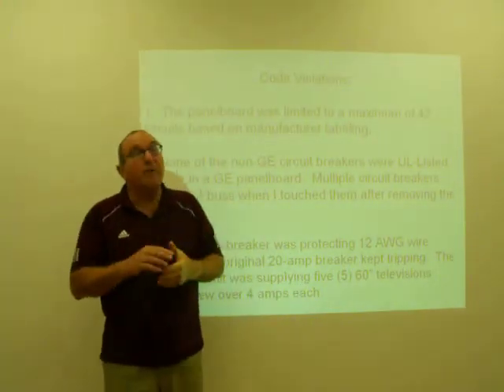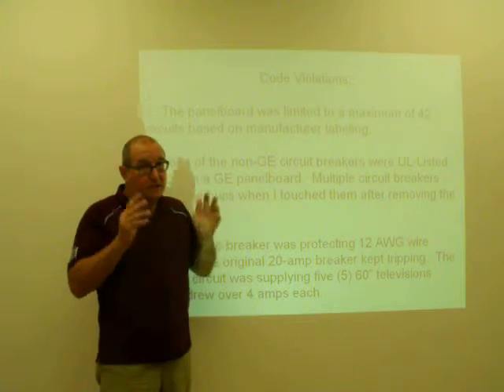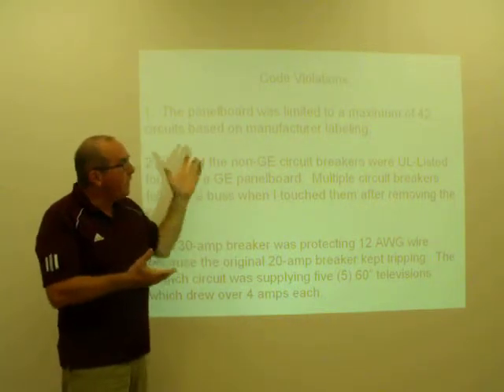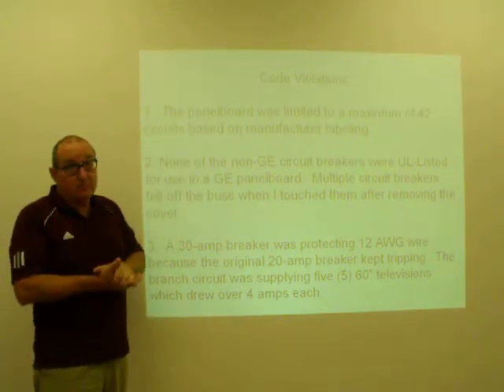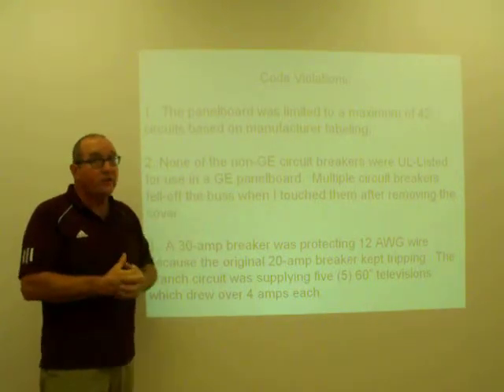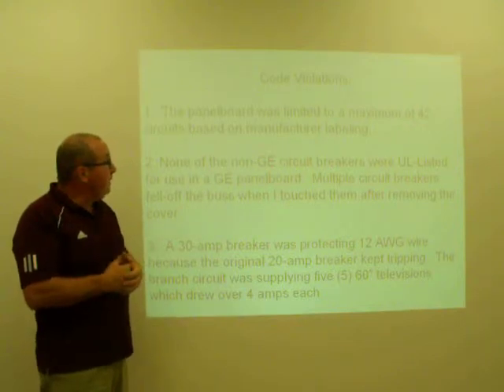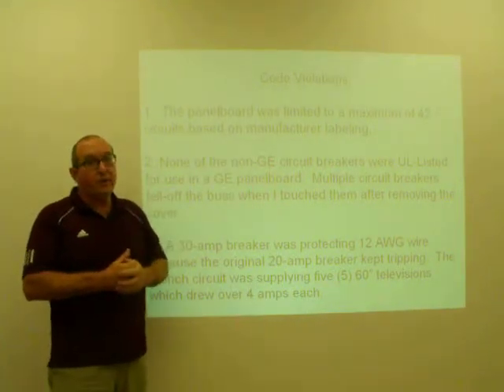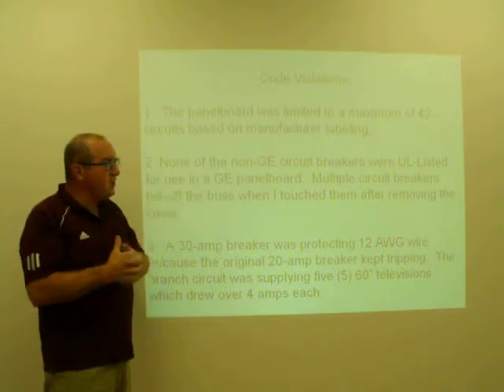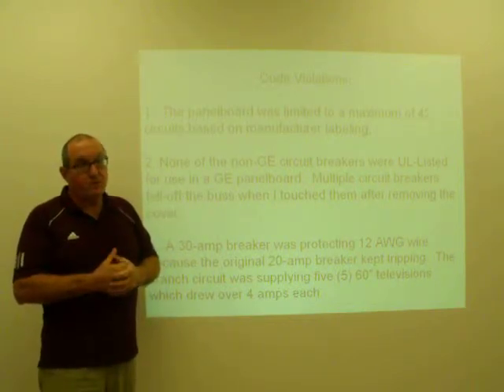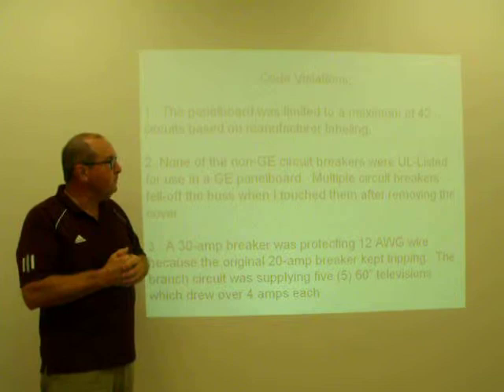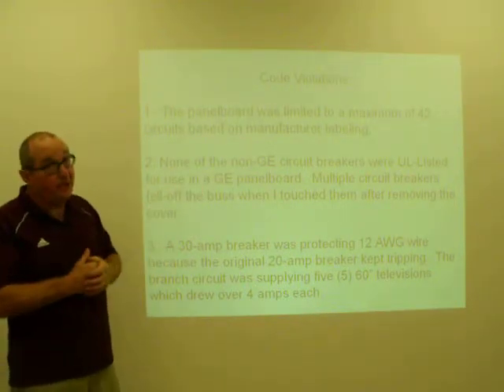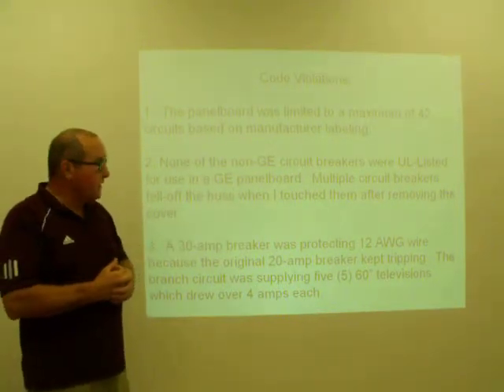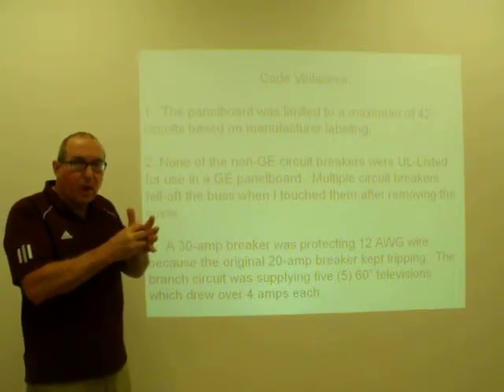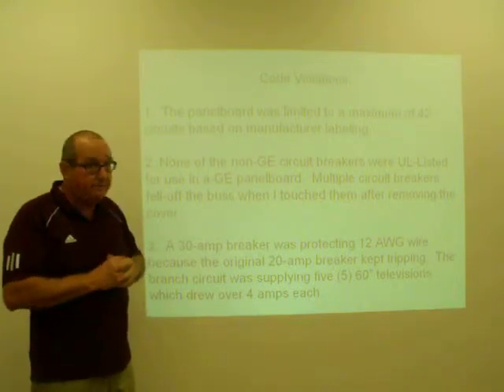Well, these are some of the code violations I found. I can't possibly go through all of them. What I have mentioned, it was a 42 circuit panel board. So installing more than 42 circuits in that panel board was a violation of the listing of that panel board. None of those non-GE breakers were UL listed for use in a GE panel board, which would have been so-called classified breakers. Multiple circuit breakers fell off the bus when I touched them, because they just simply were not grabbing the bus bar as tightly as they should have.